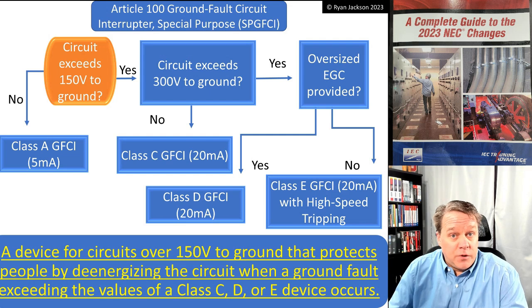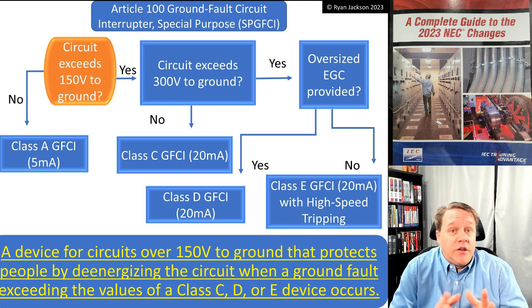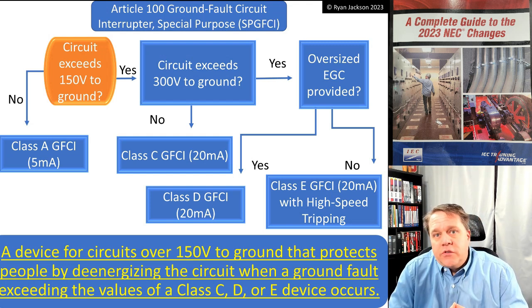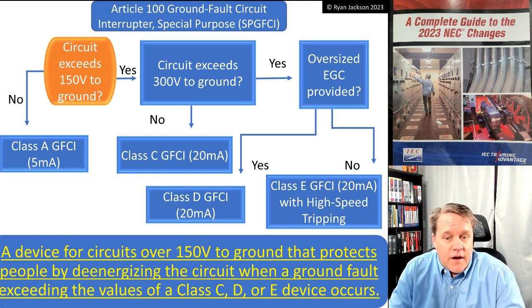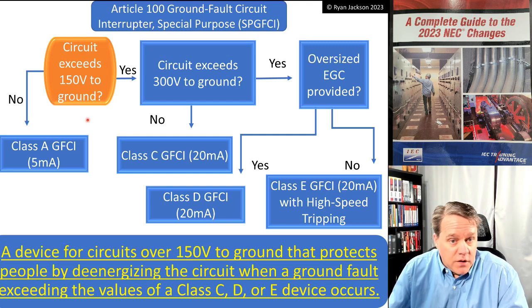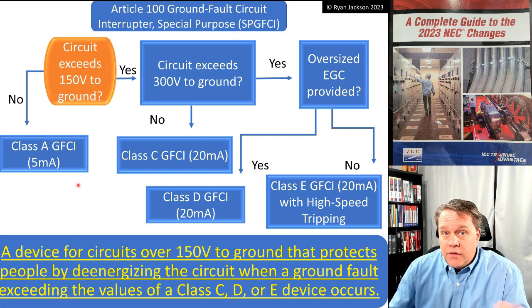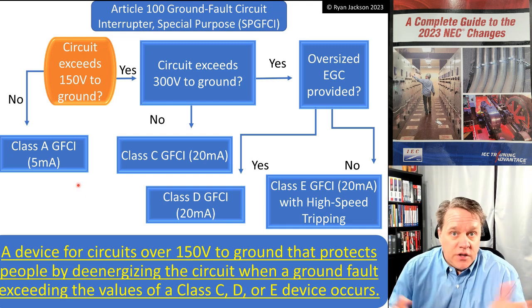We're going to call Class C, D, and E devices special purpose GFCIs. Looking at the definition first: a special purpose GFCI is a device for circuits exceeding 150 volts to ground that protects people by de-energizing the circuit when a ground fault exceeding the values of a Class C, D, or E device occurs. On my flowchart — does the circuit exceed 150 volts to ground? If not, you use a Class A GFCI.